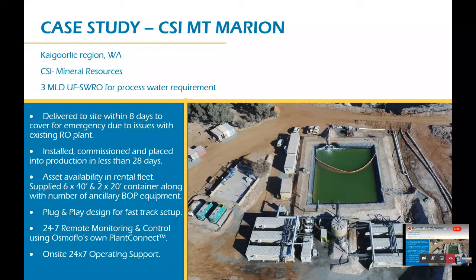They needed a 3 megalitre UF, RO water plant, and part of the solution we offered them included 6 by 40-foot containers, 2 by 20-foot containers, along with a number of skids for BOP such as self-cleaning screen filter, high flow cartridge filters, low pressure feed pumps and distribution board, etc.